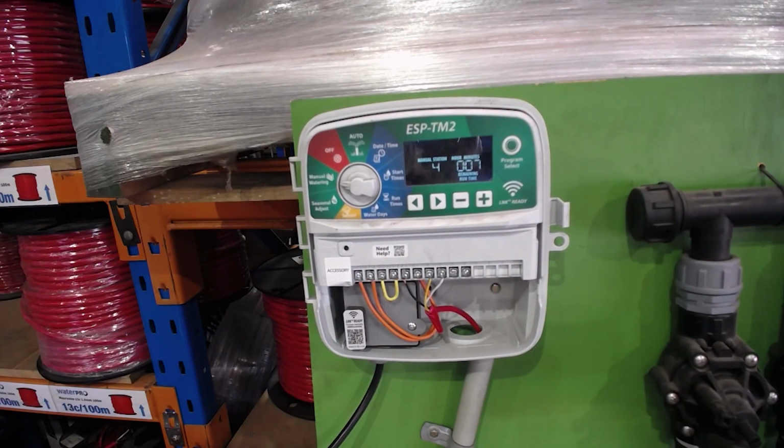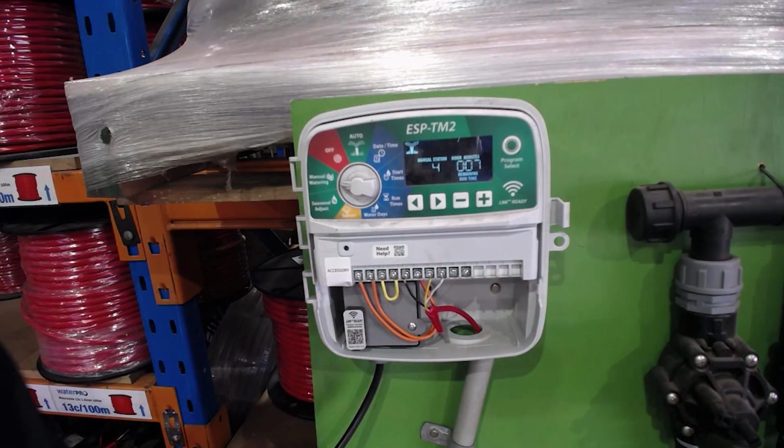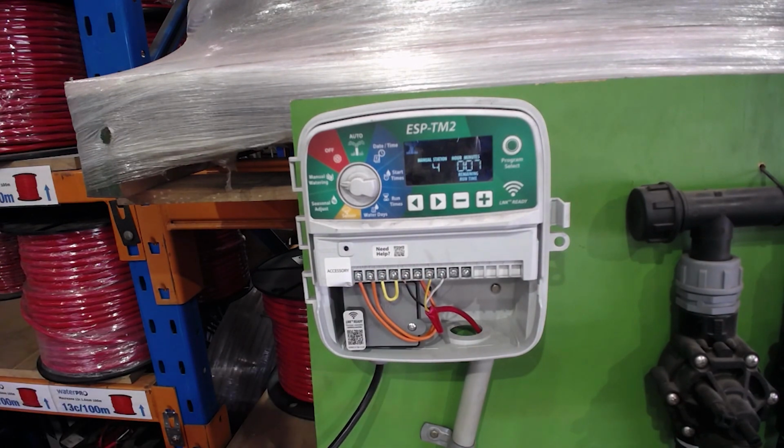What I can then do, if I know that I'm getting it there, is go to the solenoid valve at that location. If we were wanting to test our voltage drop, sometimes we've seen jobs where they've extended way too long with their cable and they're not getting any power. That's called voltage drop. There are ways of calculating that, but instead of trying to calculate it, just test it at the site.